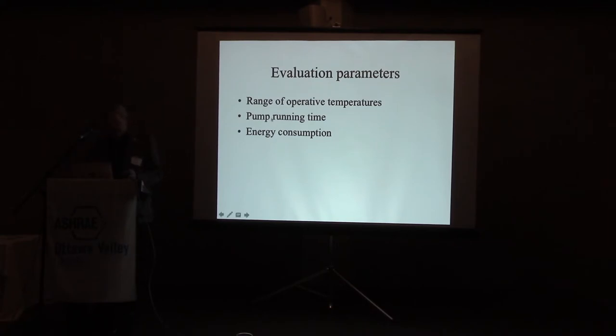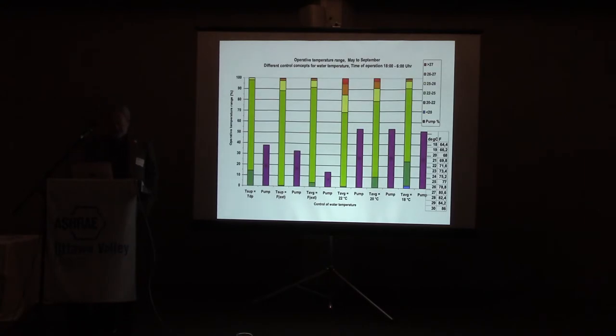Other simulations and practice have shown that we do not need to run the system the whole time. So very often we recommend just doing it during night time to have this shift in loads. If we now have these different ways of controlling, here we're trying to cool as much as possible. So the supply temperature, when needed, is the same as the dew point.